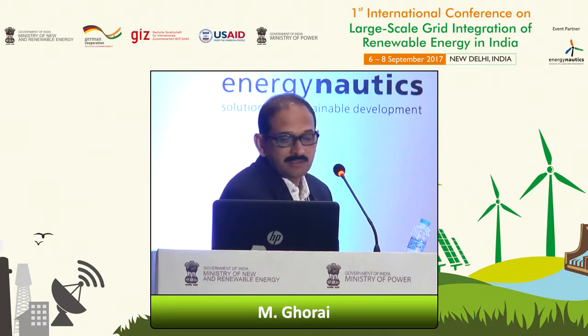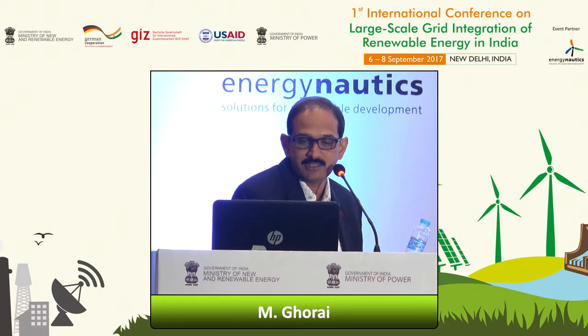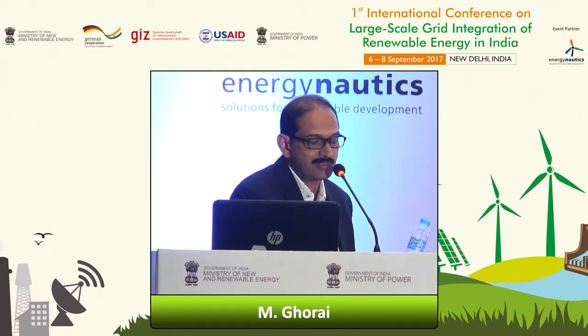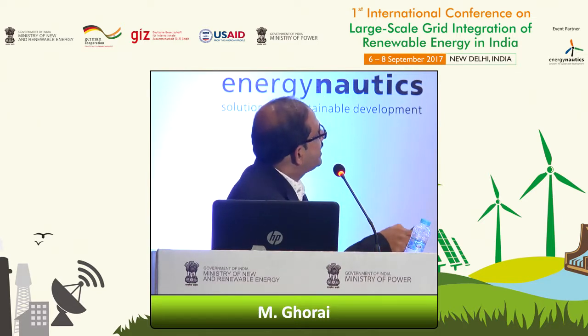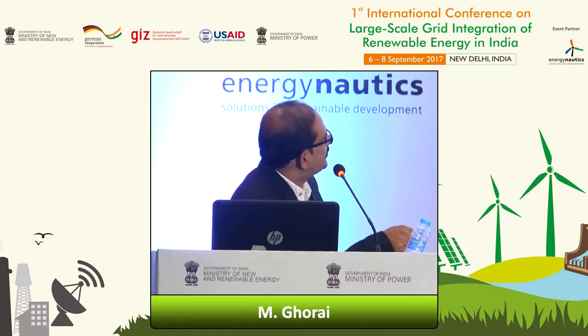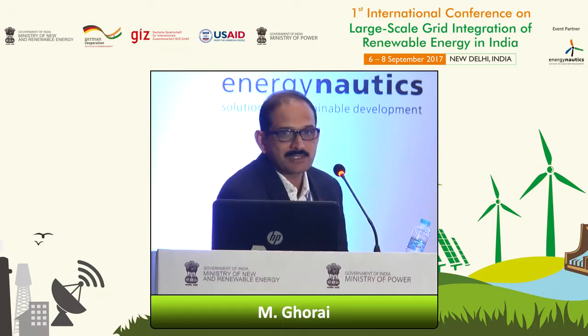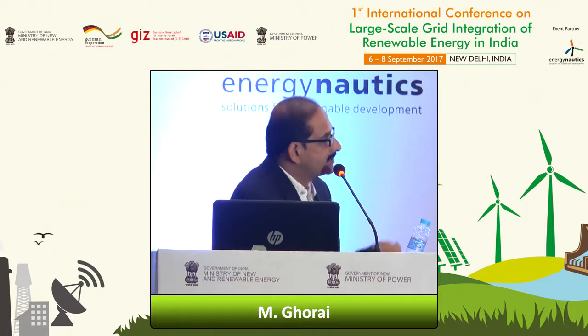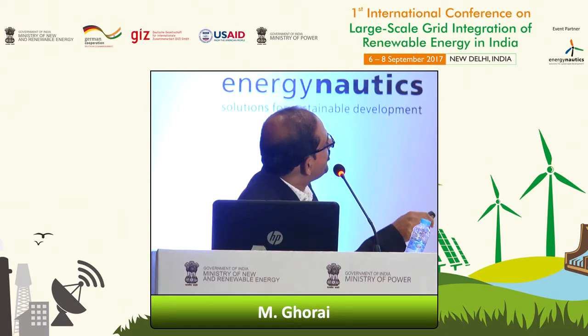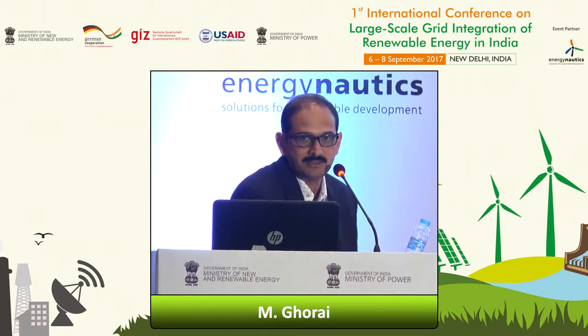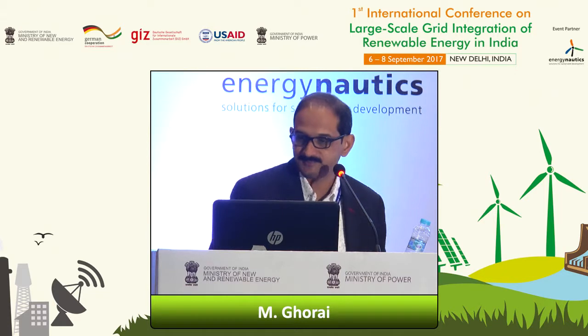These are the simulations for the power factor requirements, wherein you can see that the dotted line is the requirement. This is on the inductive side. This is on the capacitive side. This is about 66 megawatts because it's a 200 megawatt wind farm. By providing the required DVAR as well as the inductors, we are able to meet these. These are the most difficult points, and that's where the simulations help.